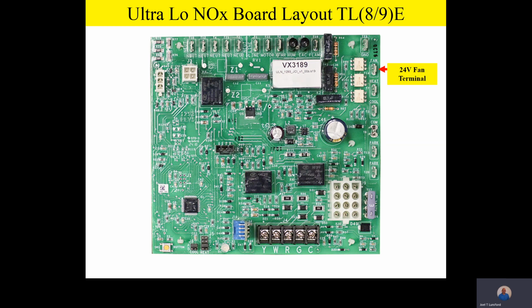Now, remember, this would be without any other cooling call or heating call or any call on the board, just a fan call only. This fan terminal will be energized when you have a G call on the board all by itself. In addition, from the factory, we typically ship this fan terminal on the low speed of the fan.